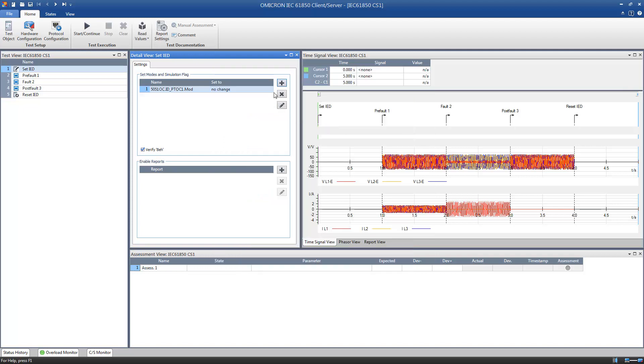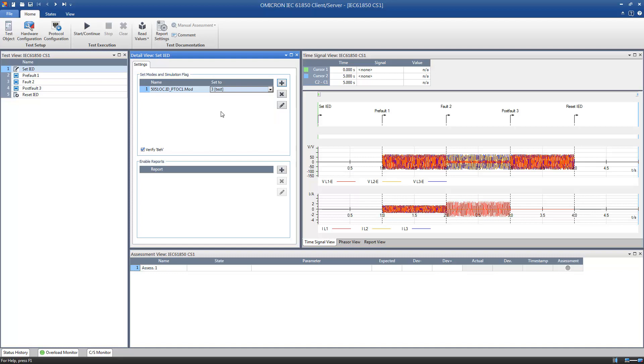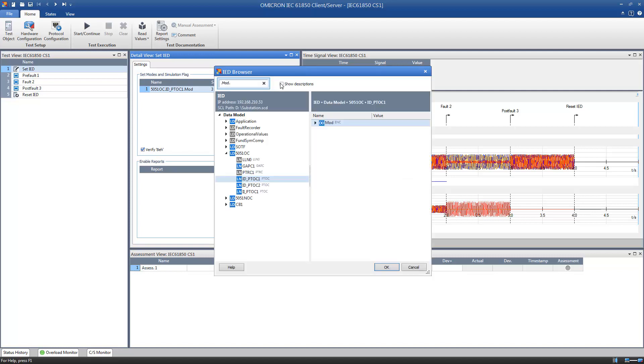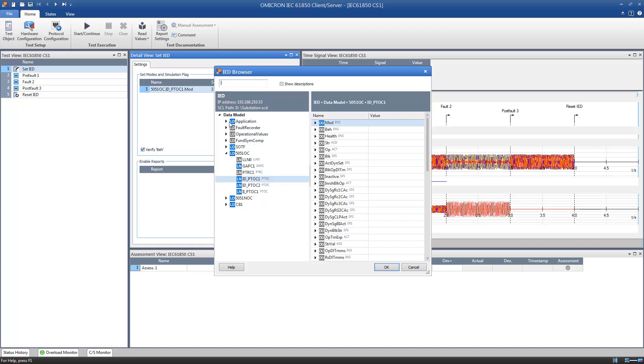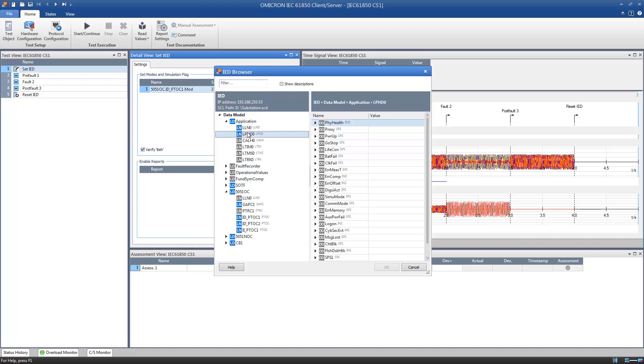The standard describes several modes: On, On Blocked, Test, Test Blocked, and Off. Using the mode Test ensures that the control center is aware that the IED is currently being tested. Furthermore, the IED can be adjusted so that it accepts GOOSE messages and sampled values streams with activated simulation bit.